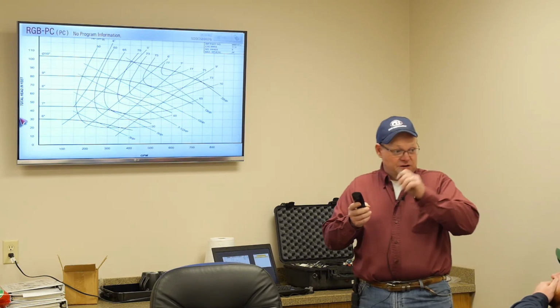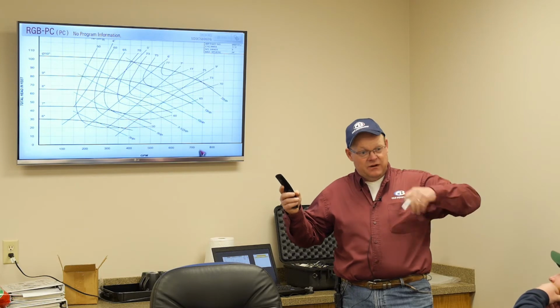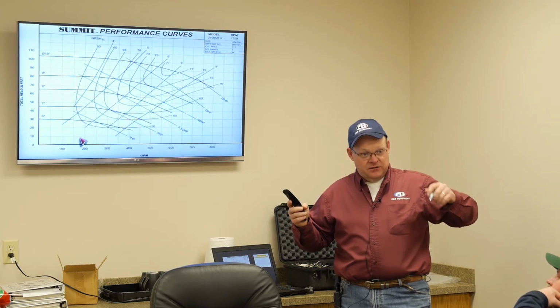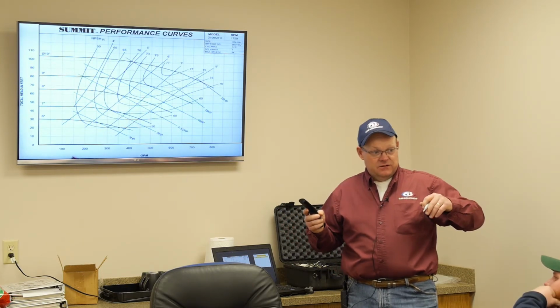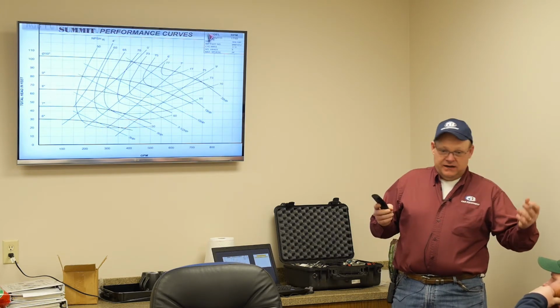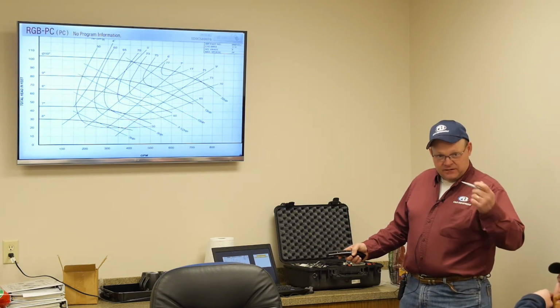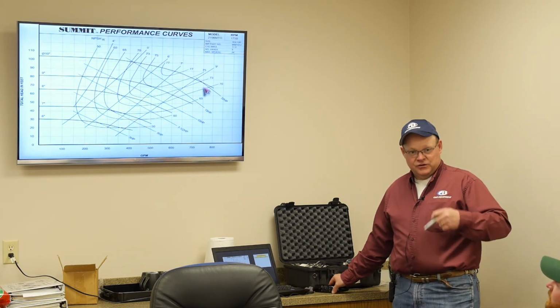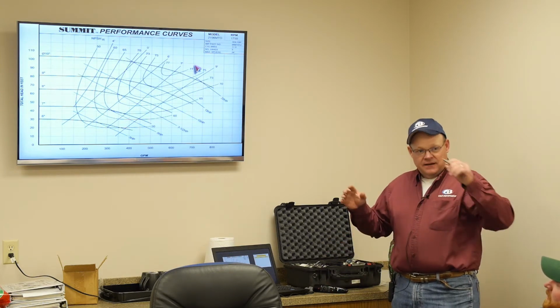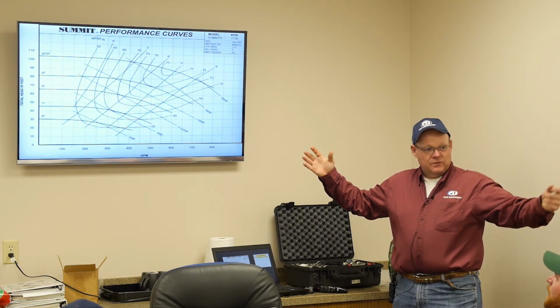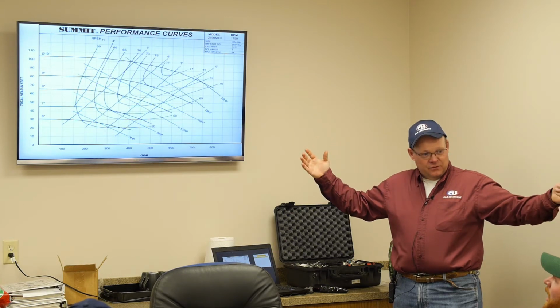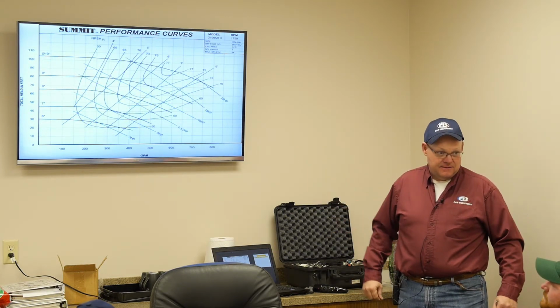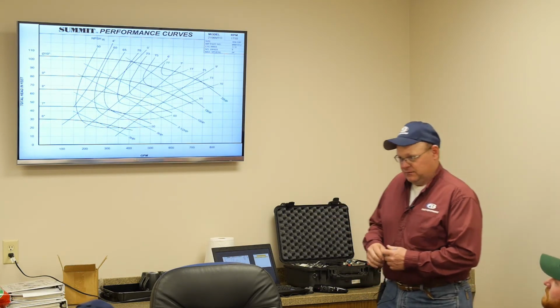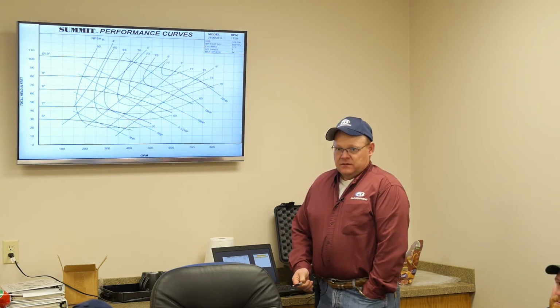And that goes back to the velocity. The faster you turn it, the bigger the wheel, the more energy it takes. You're going to be creating more pressure. It's affinity law. Don't get hung up on it. I'm just trying to get you to understand that as you increase the velocity, you can increase your flow by twice, your head by 4 times, and your horsepower by 8. It's a 2-4-8 rule. So what would happen with that 3,600?